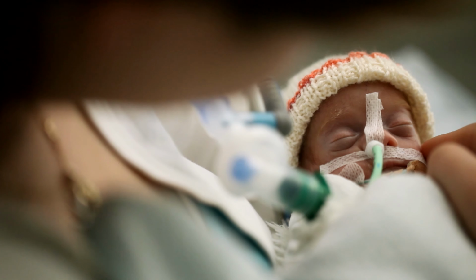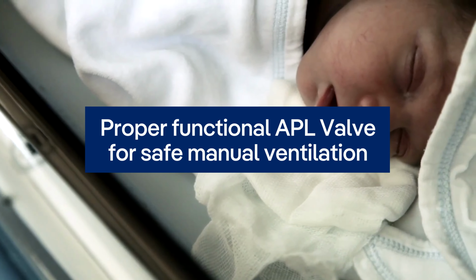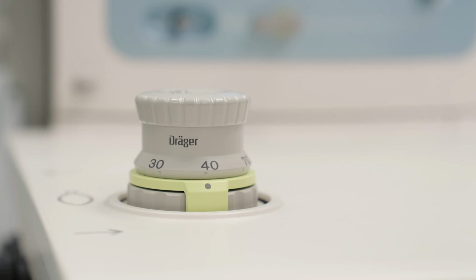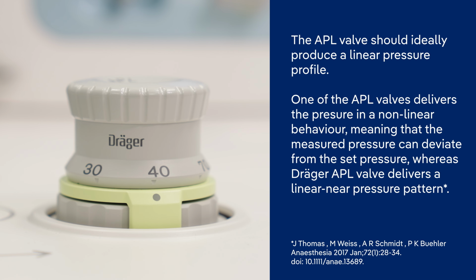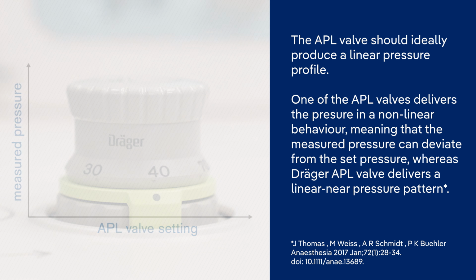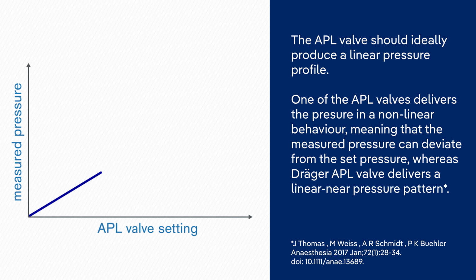Children's lungs are very vulnerable, and therefore when ventilating a child in manual spontaneous mode, the precision of the APL valve is highly important. The APL valve should ideally produce a linear pressure profile so that the pressure in the system should precisely correspond to the set value. Nevertheless, a recent study found that one of the two APL valves compared in this study delivers pressure patterns that can deviate from the intended pressure by the user, thus not allowing for safe bag-assisted ventilation. Whereas the Dräger APL valve delivers a linear pressure profile, and the delivered pressure never exceeded the set APL valve value.